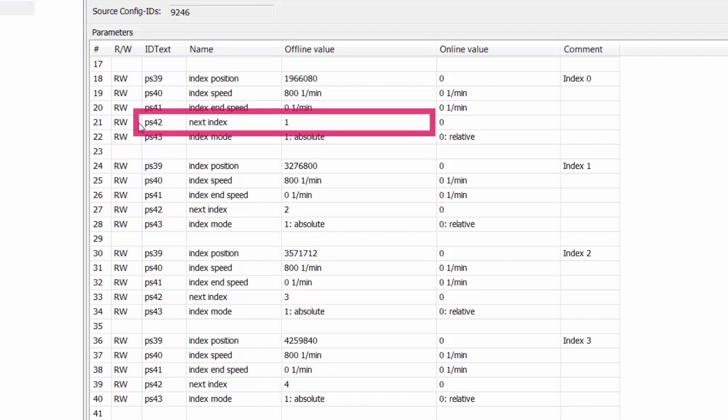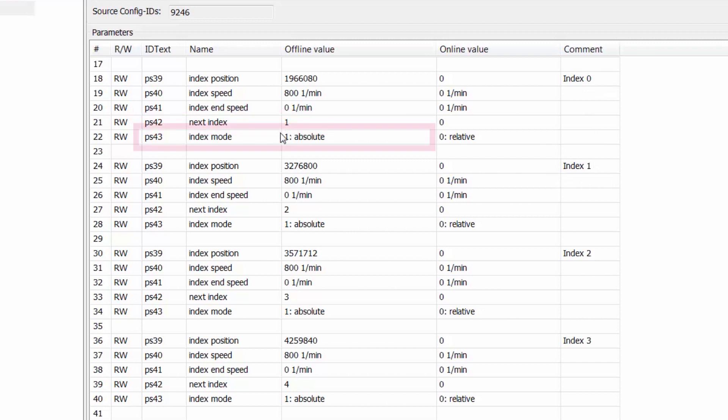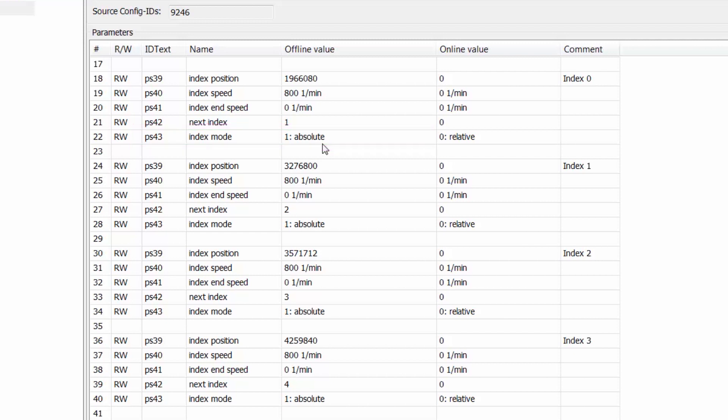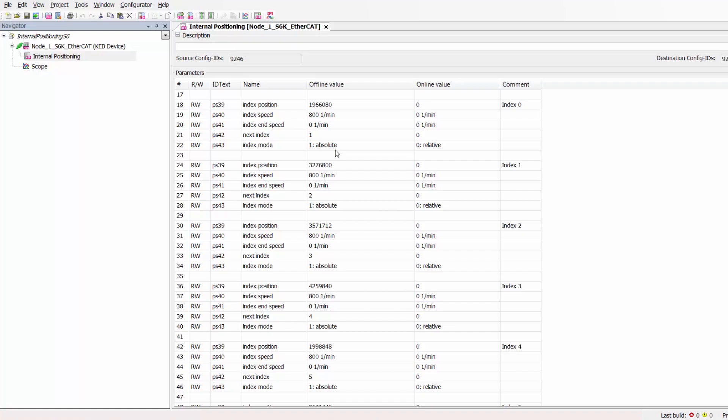The fourth parameter PS42 next index shows the parameter that is next up in the sequence of positioning. In the case of our testing we are using the auto indexing positioning mode so once the index zero position is obtained the drive will automatically start to sequence to the index one position. The fifth parameter is PS43 indexing mode and this is where you can select absolute versus relative positioning. For the case of our test and our six indices we are going to select absolute positioning mode for all of them. For your setup you can choose absolute or relative for any of your indices and use them interchangeably. Once you finalize the programming for your index zero you can copy and then just gently tweak the programming for the following indices that you need for your positioning. And once you incorporate all of the indices that you need you are ready to download the parameter list and start your positioning.